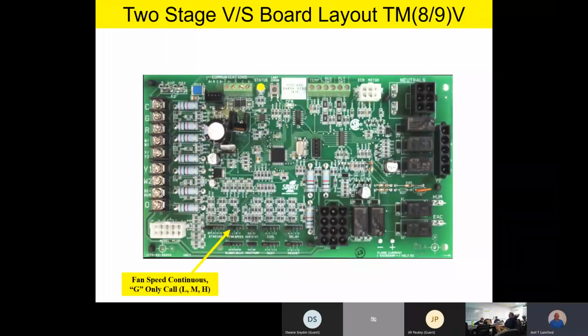Over here we have what we call fan speed. That fan speed is for your continuous fan if you have a G call only. Let me say that again. The fan speed gives you some nice functions for continuous filtration in the home. So let's say the homeowner has a nice electronic air cleaner, and they want to circulate air in the house all the time. So they go over to this thermostat sub-base assembly, and they go from auto to on where it says fan. They flip the fan on all the time.